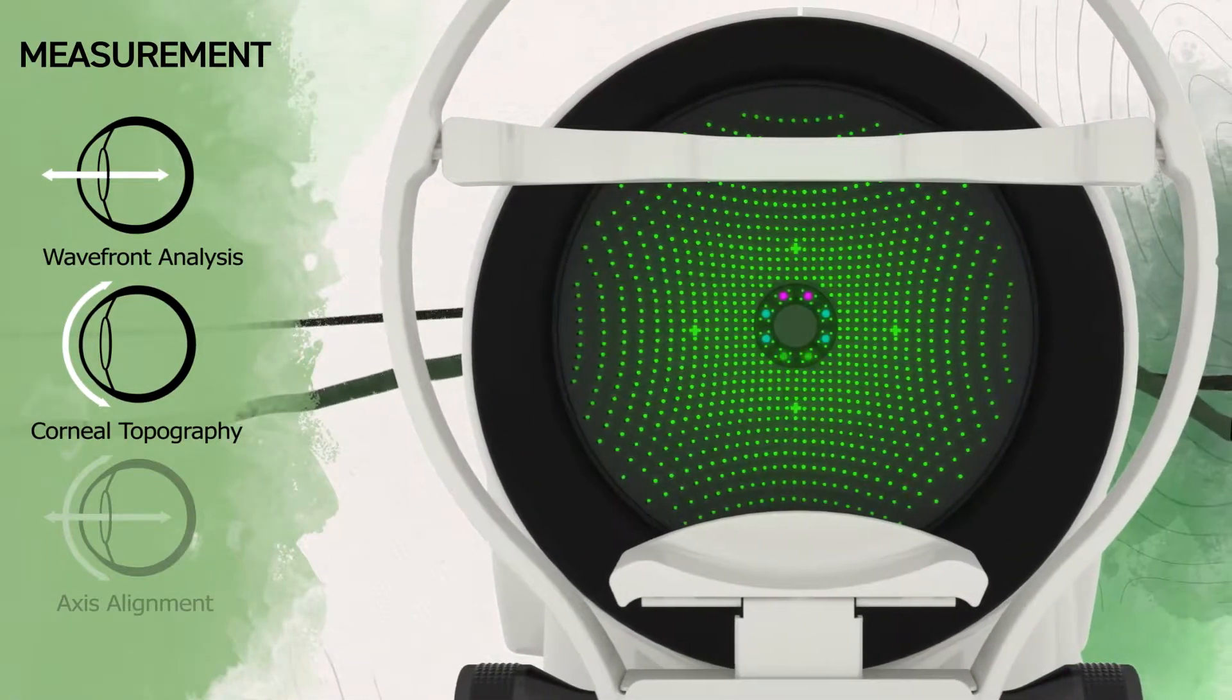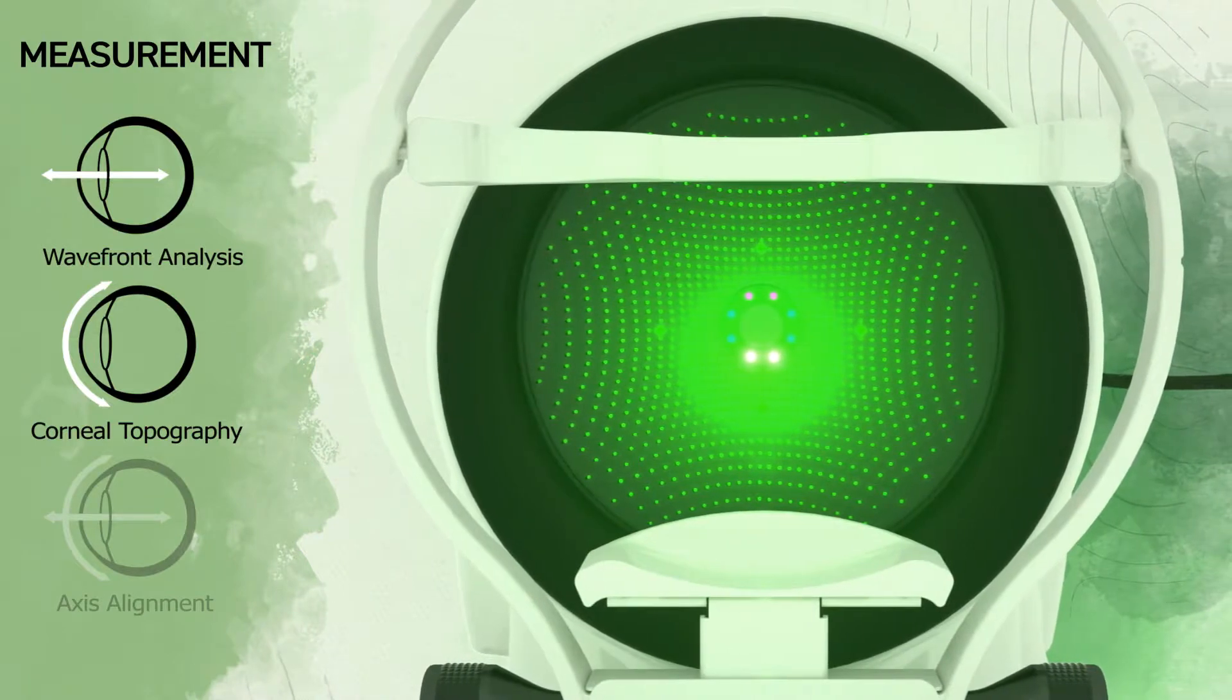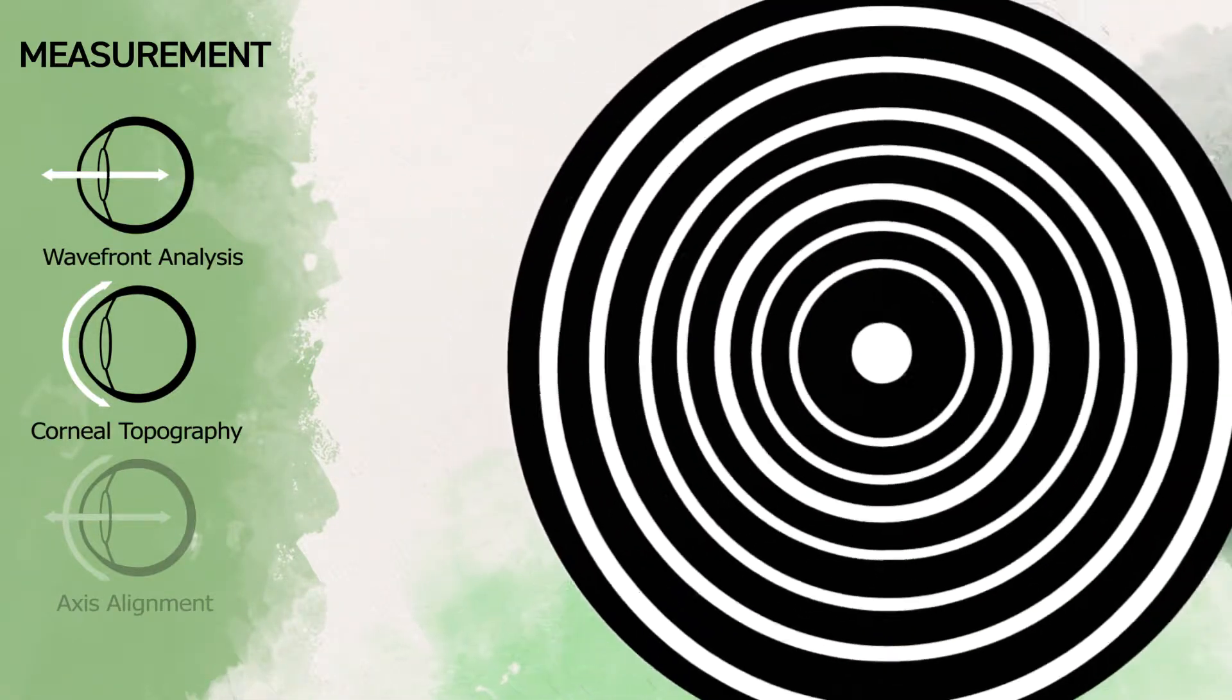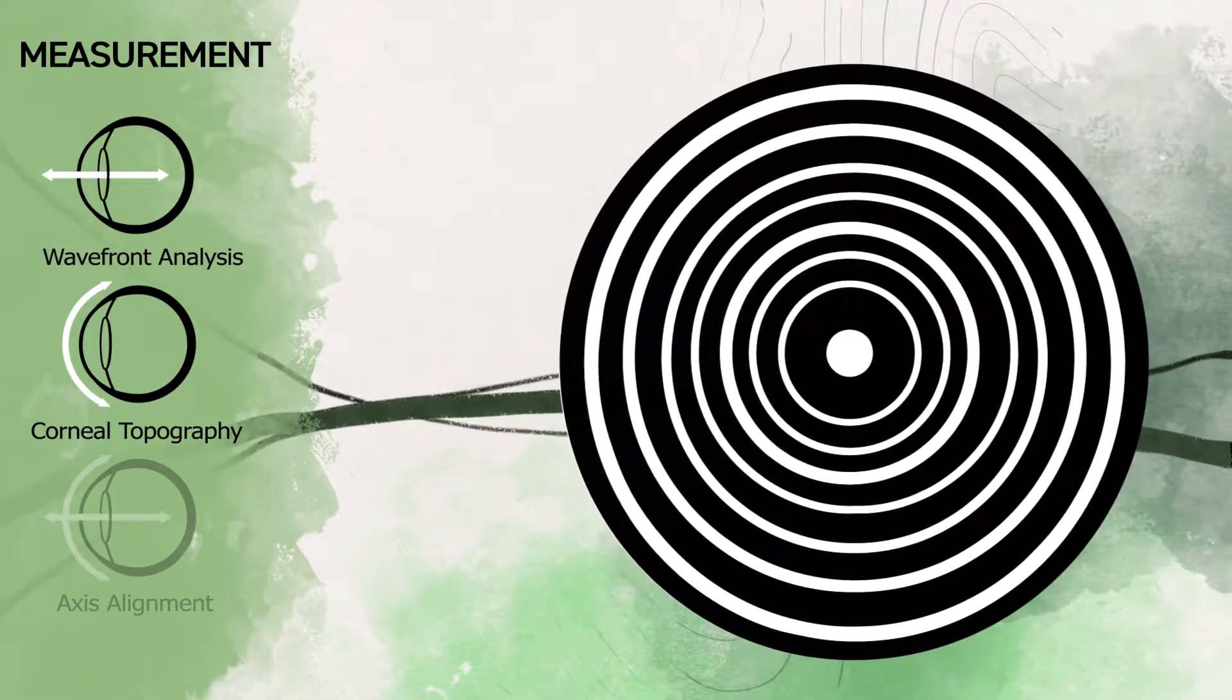This maps the cornea by projecting a pattern of spots that measure the x and y slopes at each point, instead of relying on a placido disc topographer which only measures radial slope along its concentric rings.